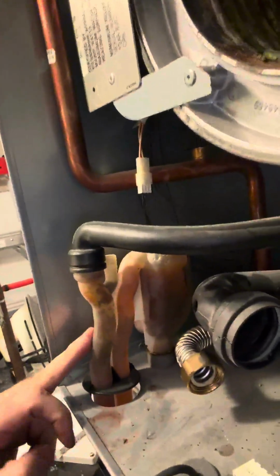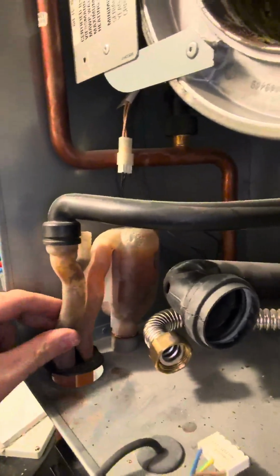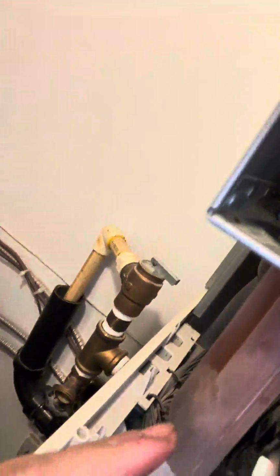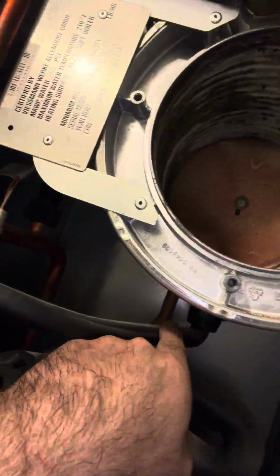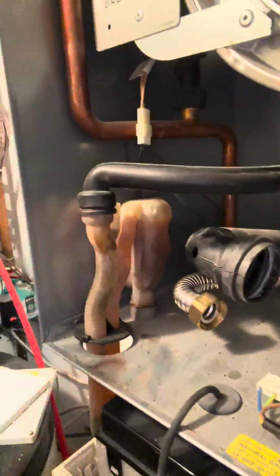Okay, so I cleaned the heat exchanger. Now it's clean. The next step is I'm gonna clean the P-trap for this Viessmann boiler. This sometimes gets plugged, which I can see from here. It's dirt down here. From here, the condensate acidic water comes into the P-trap and goes up to this drain, and then goes all the way to the drain. So the next step is cleaning this, and then basically replacing the igniter.